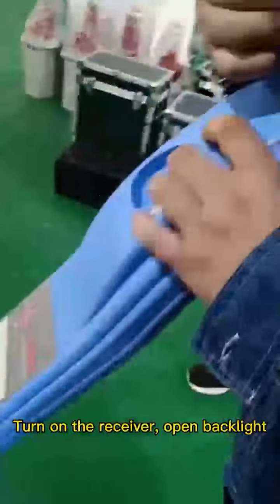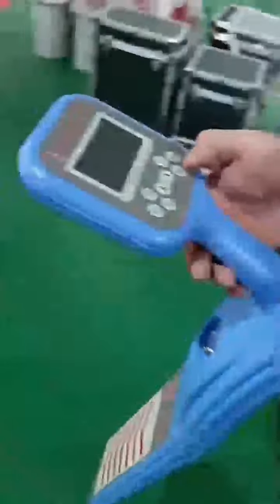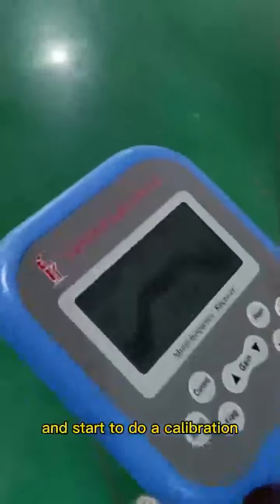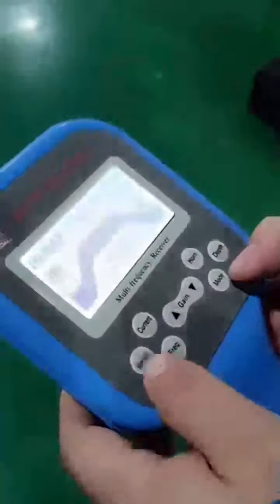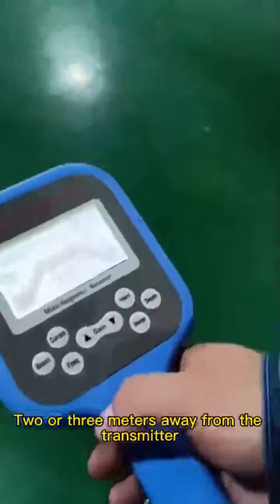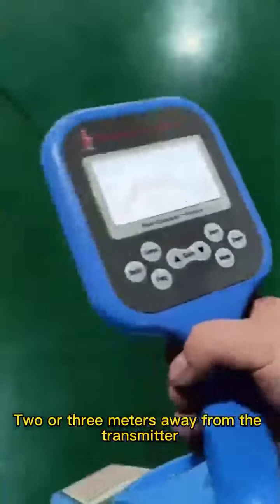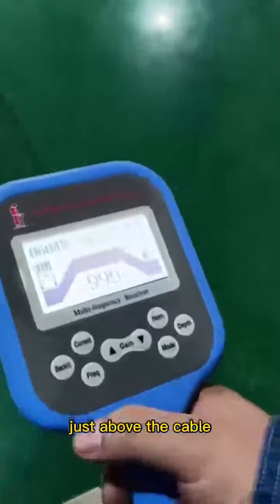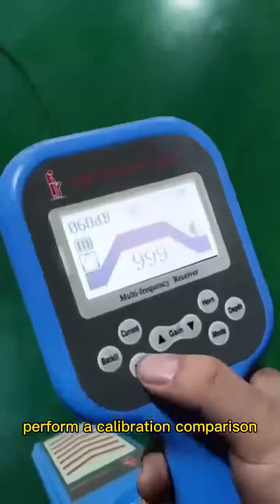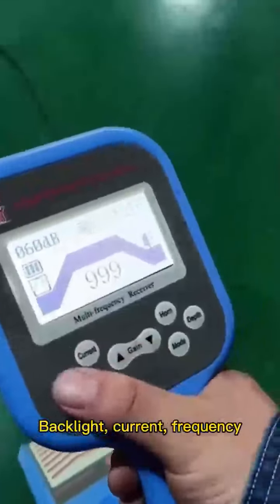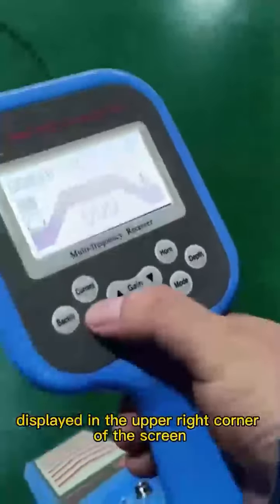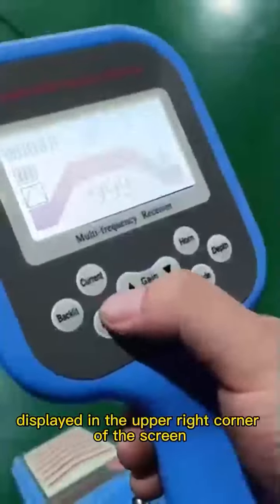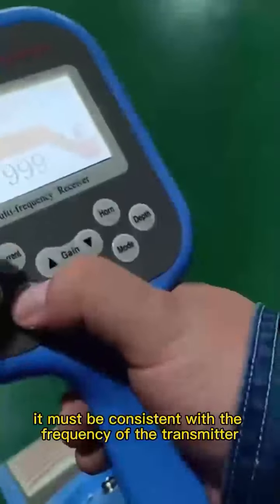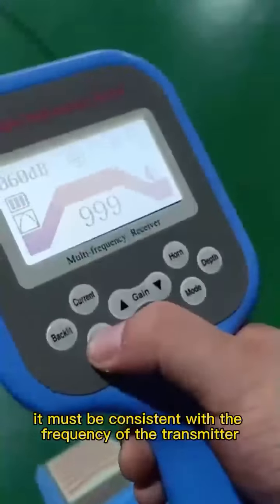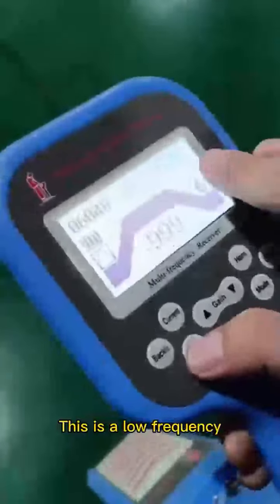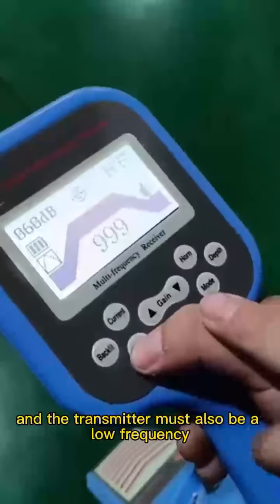Turn on the receiver, open backlight, and start to do a calibration. 2 or 3 meters away from the transmitter, just above the cable, perform a calibration comparison. Backlight, current, frequency, displayed in the upper right corner of the screen. It must be consistent with the frequency of the transmitter. This is a low frequency, and the transmitter must also be a low frequency.